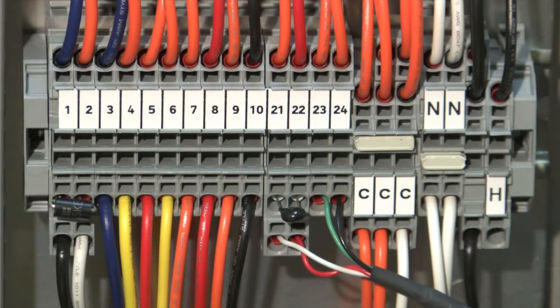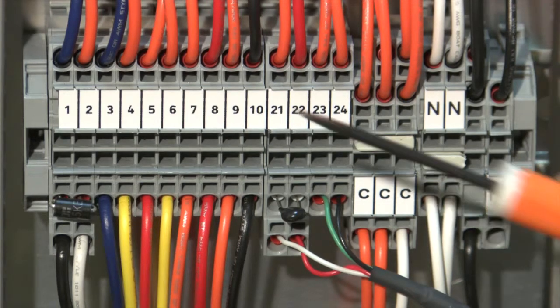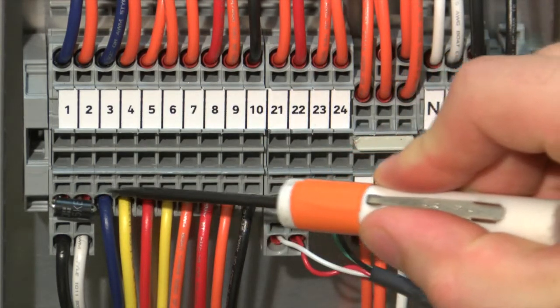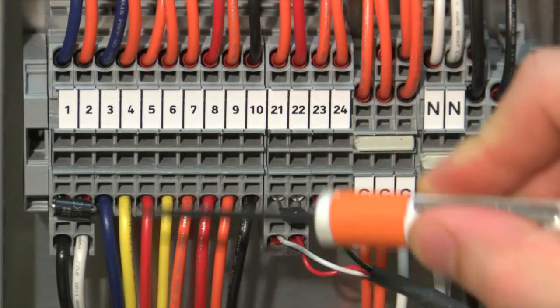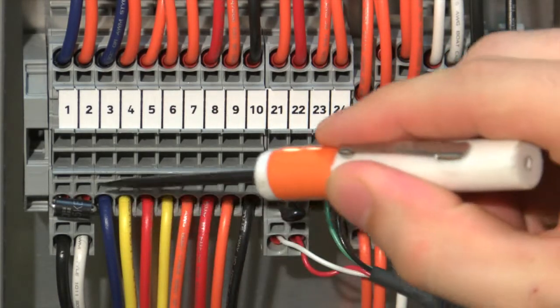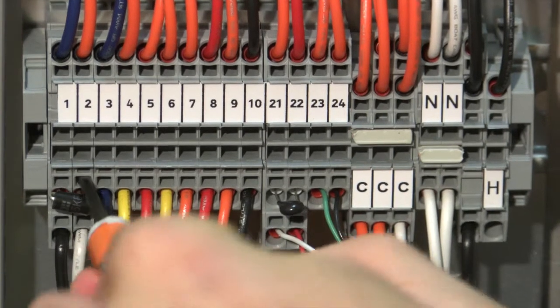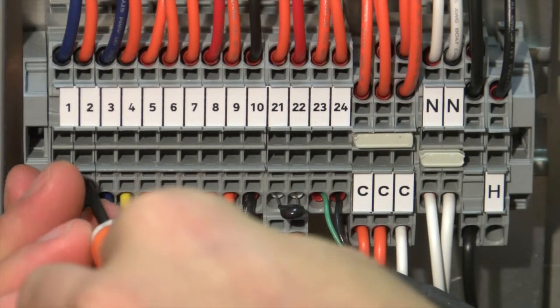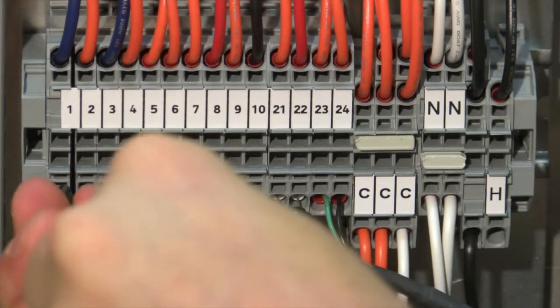If you have a blown fuse that you replace with a new fuse, and this new fuse immediately blows, you're going to want to check your surge arresters, as that is likely the culprit. To check a surge arrestor, it is best to remove it from the terminal block. To remove it from the terminal block, you will notice the small slits just above it. Using a small tech screwdriver, insert it into the block, and you can remove each side of the surge arrestor.